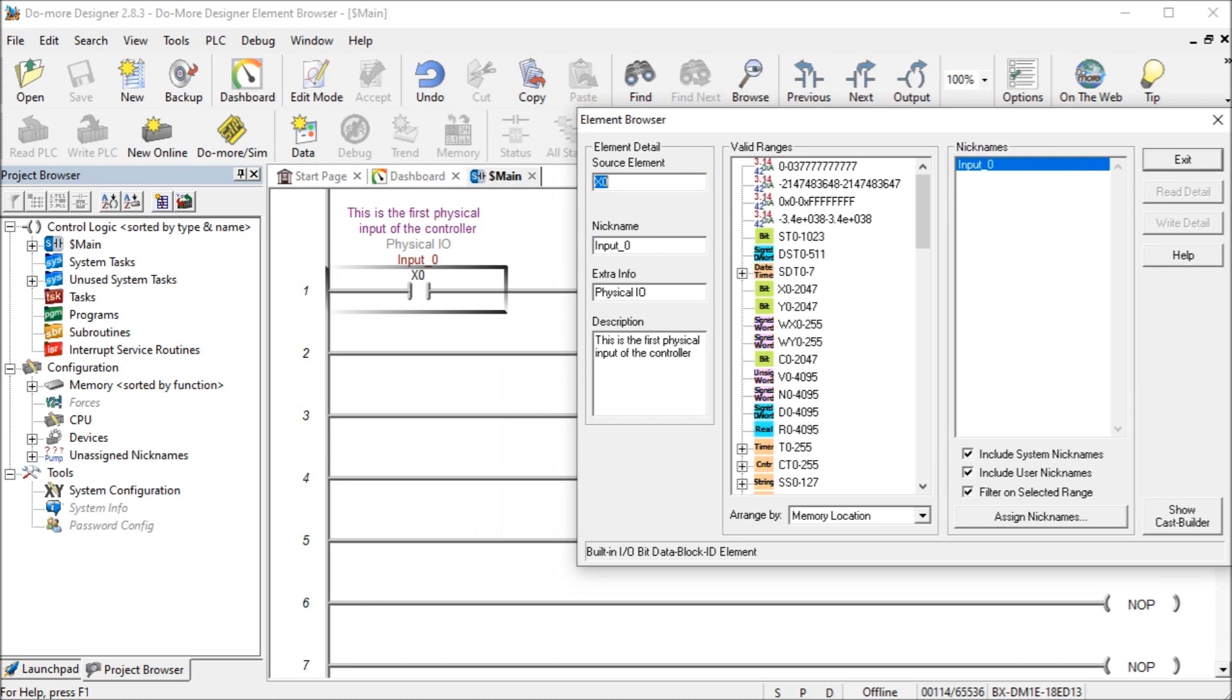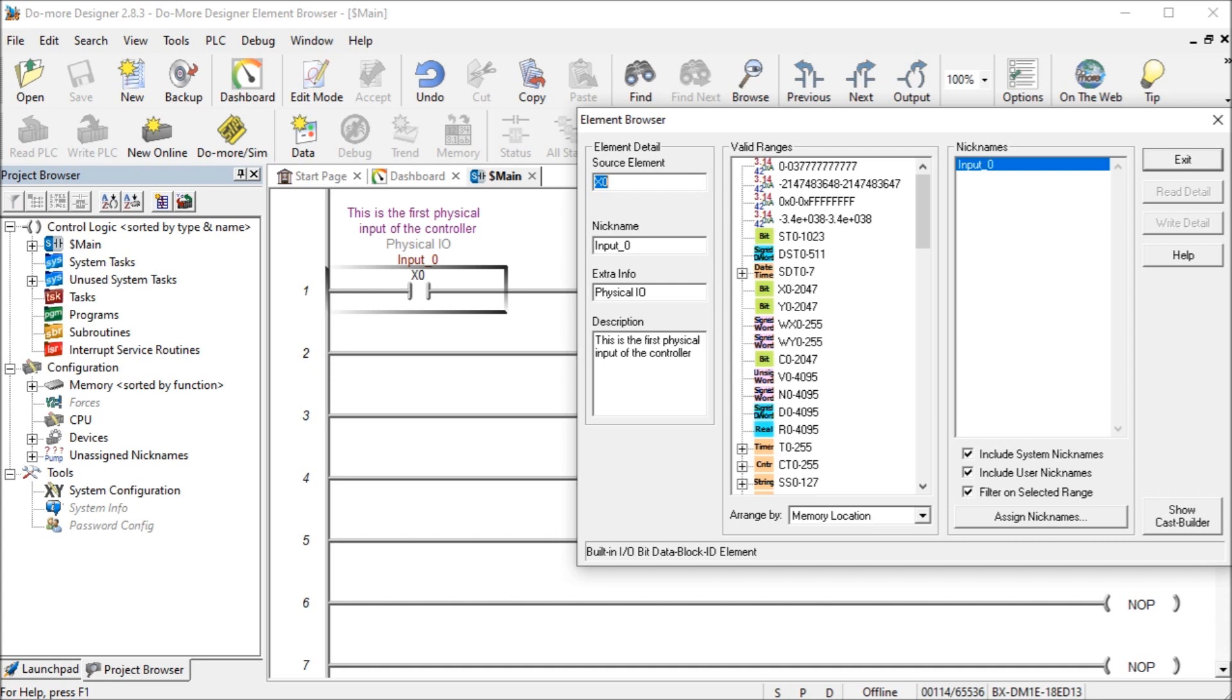In our source element, this field is always displaying the current selected element. If the element is an unassigned nickname, the element source field will be blank. Now nickname, nicknames must be unique and can be one to 16 characters in length. Nicknames must begin with an alphanumeric character or an underscore. Nicknames consist of any combination of alphanumeric characters and underscores with no spaces or punctuation marks are allowed. It must begin with a letter or an underscore. Extra info is a 16 character user assigned name for an element. If the extra info field is being used as symbolic constant, this will contain a numeric entry. In description, a 132 character field can be used to provide a detailed description of the element.